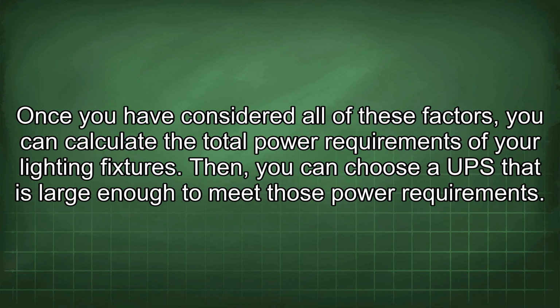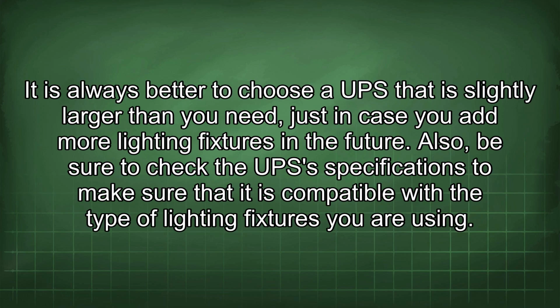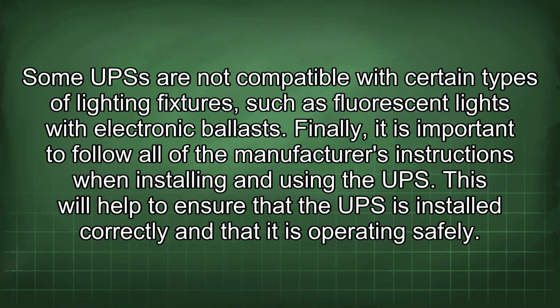Once you have considered all of these factors, you can calculate the total power requirements of your lighting fixtures. Then you can choose a UPS that is large enough to meet those power requirements. It is always better to choose a UPS that is slightly larger than you need, just in case you add more lighting fixtures in the future. Also, be sure to check the UPS specifications to make sure that it is compatible with the type of lighting fixtures you are using. Some UPS are not compatible with certain types of lighting fixtures, such as fluorescent lights with electronic ballasts. Finally, it is important to follow all of the manufacturer's instructions when installing and using the UPS. This will help to ensure that the UPS is installed correctly and that it is operating safely.